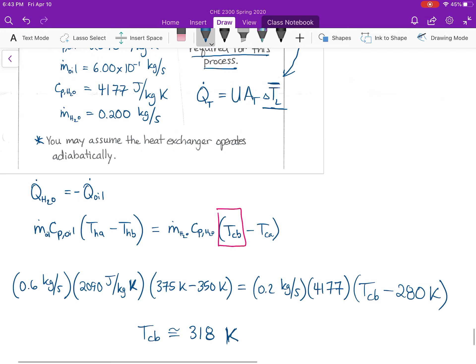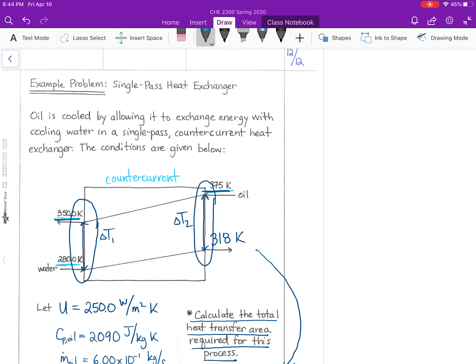This is just delta T2 minus delta T1, where we can define this difference as our delta T1, drawn right here, and this other difference as our delta T2. So it's delta T2 minus delta T1 divided by the natural log of those quantities. If I do the math and plug in my numbers, I end up with a log mean temperature difference of 63.3 Kelvin.